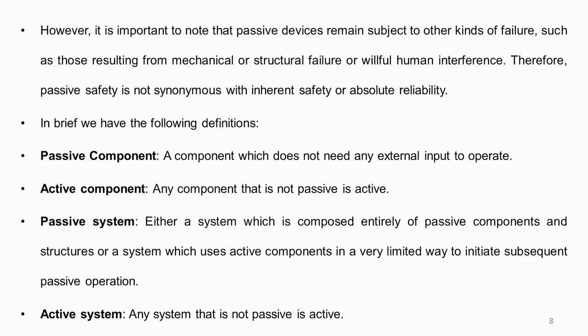Even passive devices remain subject to different kinds of failures. Take a non-return valve — it must open based on forces, but if it has not been utilized for a very long time, it could fail when really required. So let us not say that if it is a passive safe system it is absolutely safe or inherently safe — no. Still it involves a certain amount of active systems or active devices. Passive devices also need to be supervised; surveillance needs to be conducted even on passive devices.